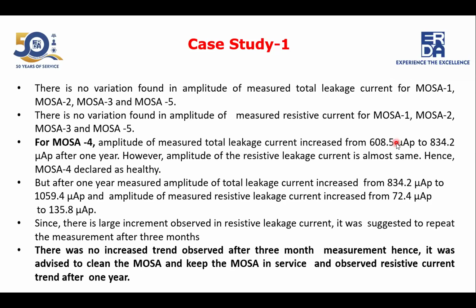That's why we declared MOSA 1, 2, 3, and 5 as healthy. Whereas for MOSA 4, the amplitude of measured total leakage current increased from 600 microampere to 834 microampere after 1 year, and then again to 1059 microampere. Since there was a large increment observed in the resistive current, it was suggested to repeat the measurement after 3 months.